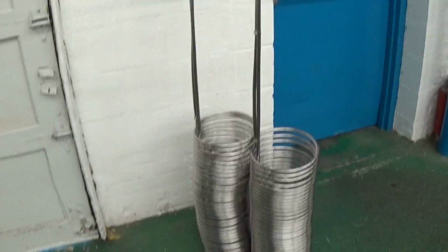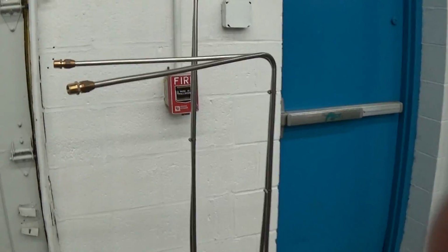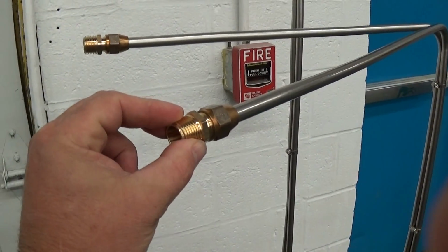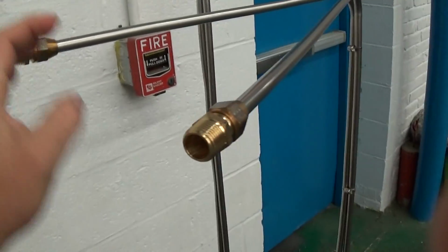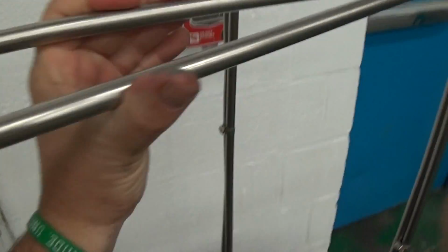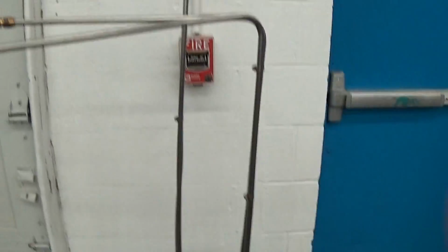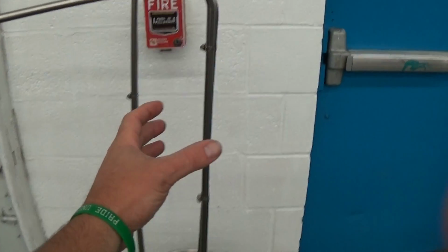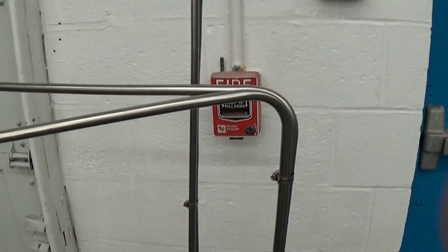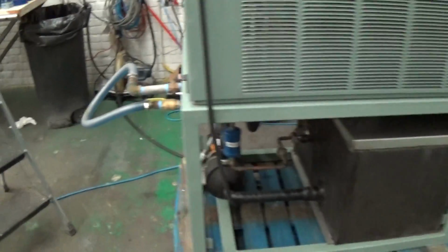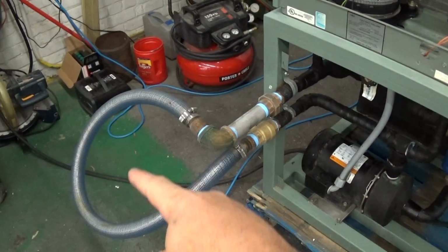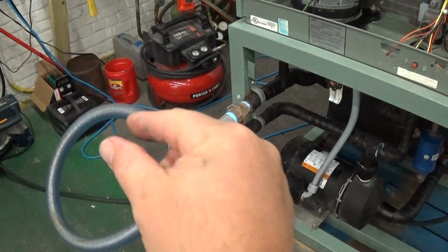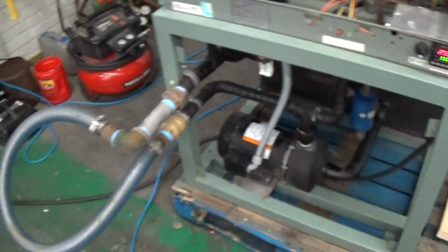These are the coils. They look a little bit squished when they're just resting here, but these will ship out with the chiller. You got 1/2-inch NPT fittings, male threads here, and we'll have a little clamp to hold these together, but basically this one will sit on top of the taller one, and you probably want to just clamp them all together and then make your connections. You're going to have your outflow from here go to a T, and then your output flare out to the 2 inputs of that, and similar on your return.